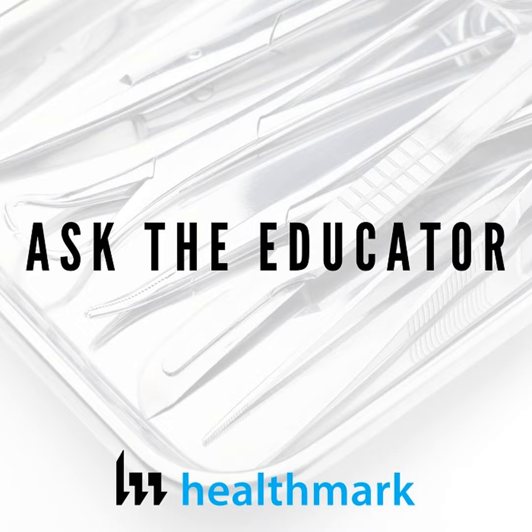But you just got to start somewhere, and you might find out, especially if you have old equipment, that it fails that first time, and it's discouraging because you have to figure out now how to troubleshoot, and that's okay. I gave a whole list of things you can check right away, right there in your department, from O-rings to connectors, detergents, all of this stuff that you can do right there in your department before you even call service. And hopefully you can take care of some of that low-hanging fruit and then move on to the more complicated things if need be. But definitely start by getting that test going first.